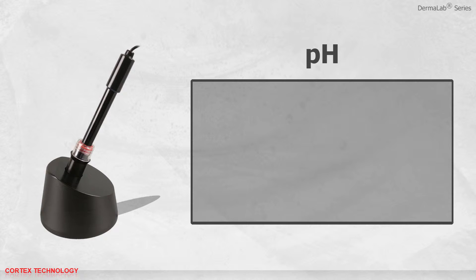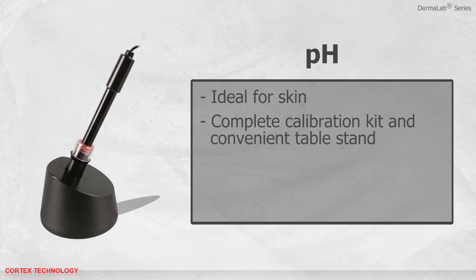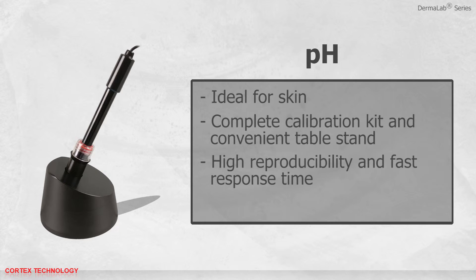The pH probe features a surface type, which is ideal for skin. It comes with a complete calibration kit and a convenient table stand. It offers high reproducibility and fast response time. The DermaLab software facilitates easy calibration.